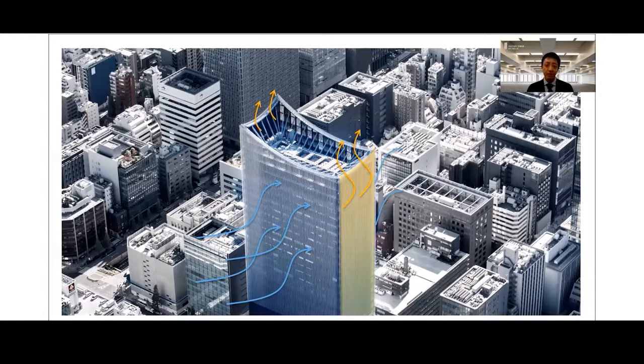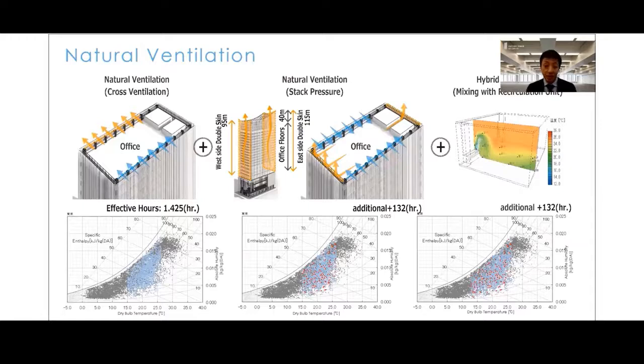The stack effect is created by the double skin configuration at the east and west side facades. The double skin was extended 30 to 40 meters up to the crown part in order to create negative pressure to draw the air from the indoor space, even on the higher office floors. It is estimated that approximately 30% of annual HVAC system operation hours are available for wind ventilation. In addition, the stack effect expands the effective period by an additional 3% during hours with low winds.